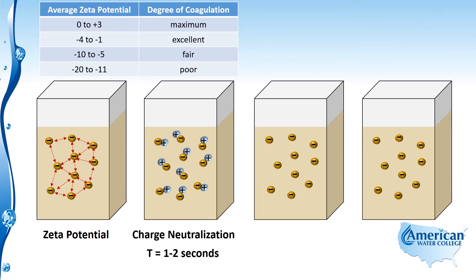As we lessen the negative charge — as the negative numbers get smaller — going up to fair coagulation, the range is minus 10 to minus 5 millivolts. As we further reduce the zeta potential to a range of negative 4 to negative 1, we consider that to be excellent coagulation. Most plants operate in this slightly negative range because they don't want to add too much coagulant, which can pass through the plant and cause issues in the distribution system. Maximum coagulation is when the average zeta potential is in the range of zero to plus three millivolts.